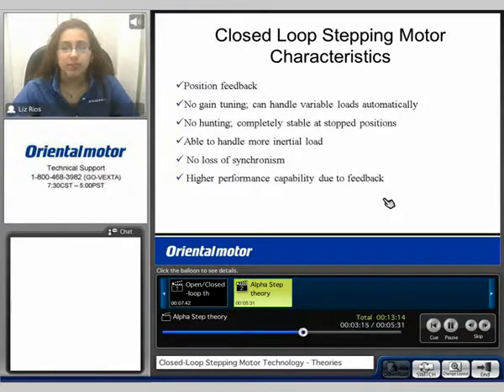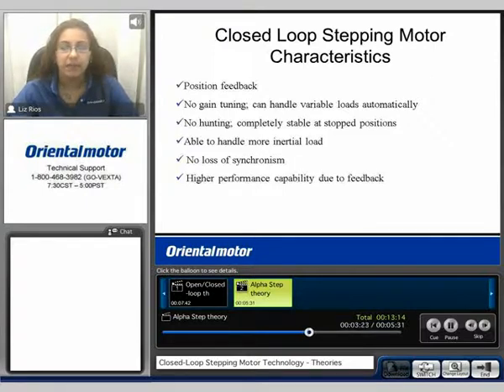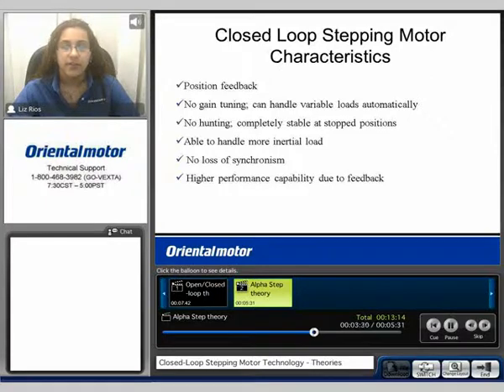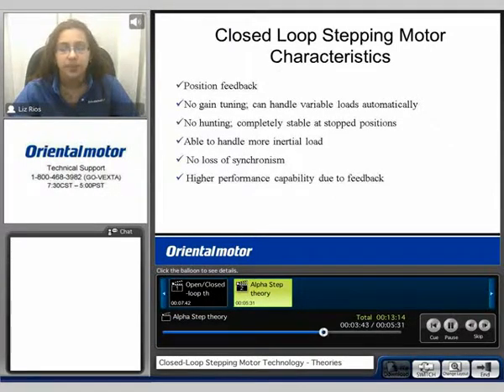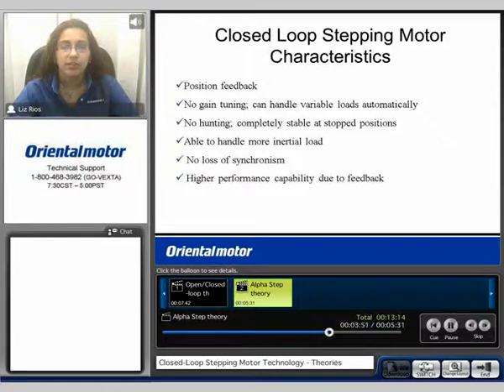Here we can see some closed loop stepping motor characteristics. The closed loop system does have position feedback. There's no gain tuning, so it can handle variable loads automatically, and there's no hunting. It's completely stable at the stop position. It's able to handle more inertial load than an open loop system. There's no loss of synchronism because of the keep-in-step method, which automatically corrects the move within the motion. If it cannot correct the move within 5 seconds, it will alarm out letting the user know. And it has higher performance capability due to the feedback.